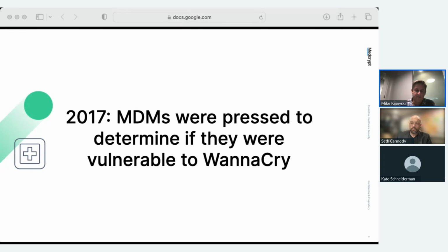I interpreted the FDA's ask for an SBOM more as asking device manufacturers to demonstrate that they know what software is in their products and that they can take action if one of their software components has a critical vulnerability in it. In other words, the EternalBlue or SweynTooth Bluetooth vulnerabilities that you mentioned in your anecdote there. First of all, a lot of Bluetooth-based devices don't get sold into hospitals; they get sold to users. And as an end user, if I have an SBOM telling me that my insulin pump has this SweynTooth vulnerability, what am I going to do with that information? There's not really a whole lot that I can do about it.